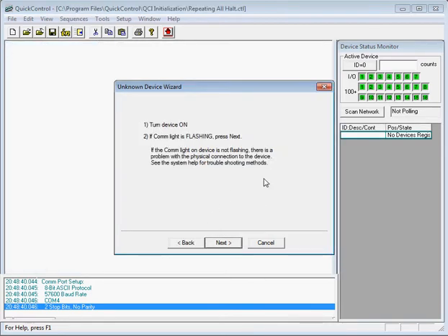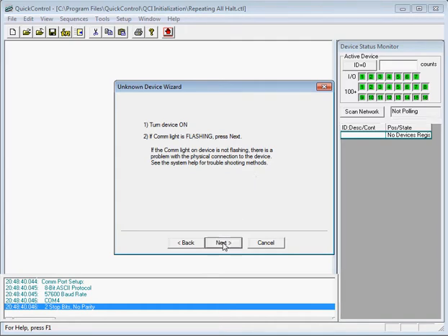Now we're prompted to turn the device on, so we'll go ahead and power on the device. As we power on, the red communication LED on the controller should be flashing at a fast rate. If it's not flashing, check that you selected the correct communication port and double-check your communication wiring. If the red COM LED is flashing, go ahead and click Next.